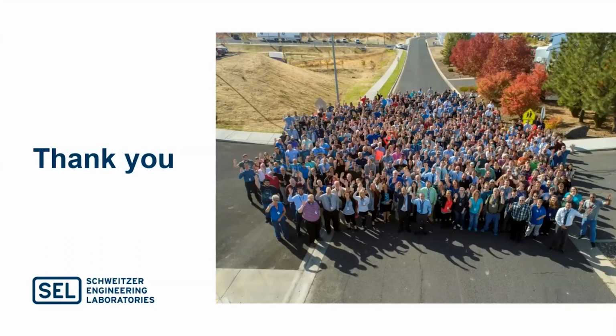Thank you. You talked quite a bit about the behavior and reliability of inverters. What is it about inverters that makes them behave so differently than traditional governors? What makes them so much more variable? Yes, the behaviors of a generator are predicated by the flux and forces in an air gap and the winding structures. That controls primarily the transfer of torque to power and the creation of a back EMF to produce voltage. The engine drives the speed of said generator, and its speed governor, typically today on the small engine size, is called an engine control unit. They may be digital, more commonly are, but not always. And those speed regulation devices commonly have just simple proportional integral derivative controls.